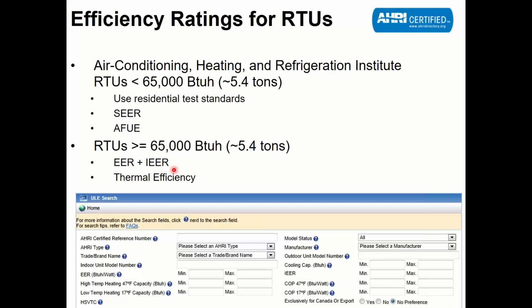That means I run this system on a 95-degree day to make 75-degree indoor. I run it at maximum capacity. I let it get stable. Then I measure how efficient it is. Peak full load efficiency. SEER or IEER are both part load efficiency things. They have a full load portion to them, but they are heavy on the part load. And I'll show you how IEER works in a minute. But it's more focused on part load.